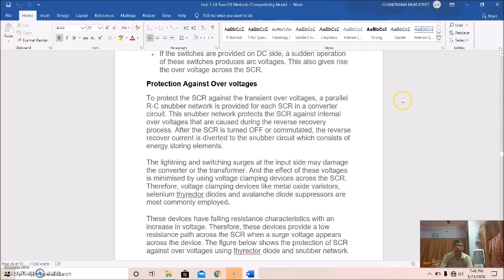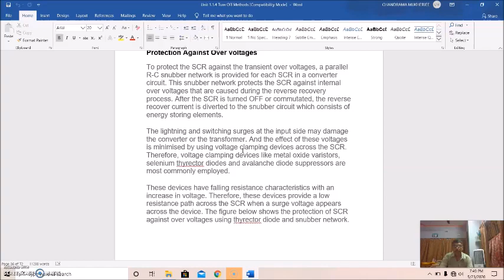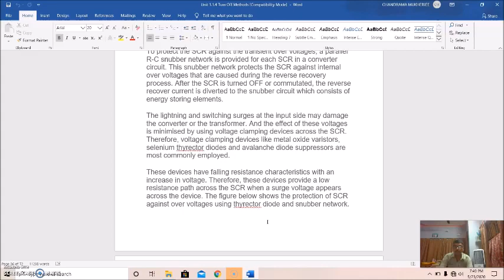Lightning and switching surges at the input side may damage the converter or the transformer. The effect of these voltages is minimized by using voltage clamping devices across the SCR. Voltage clamping devices like metal oxide varistors, selenium thyrector diodes, and avalanche diode suppressors are most commonly used. These devices have a falling resistance characteristic with an increase in voltage. Therefore, the device provides a low resistance path across the SCR when the surge voltage appears across the device.